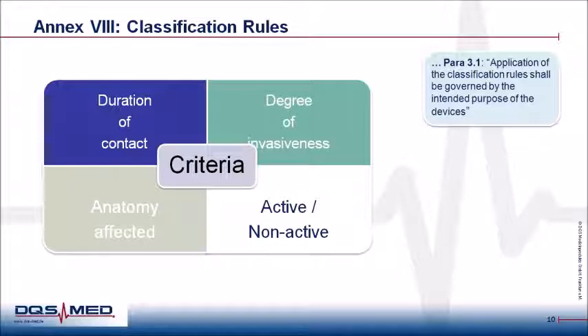It is also beneficial to note that Annex VIII, paragraph 3.1 of the MDR lists that application of classification rules shall be governed by the intended purpose of the device. That is, if your intended purpose is in brain or heart, the device will be Class 3. If not, it might be Class 2A or 2B.